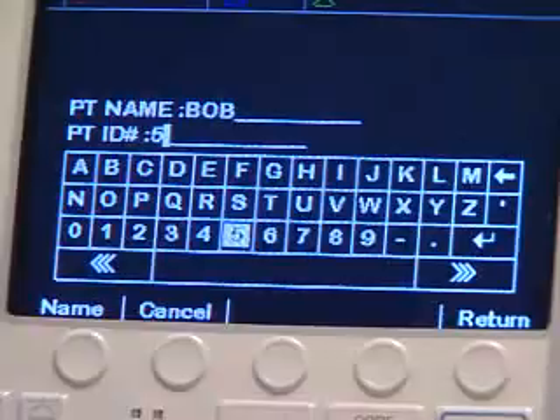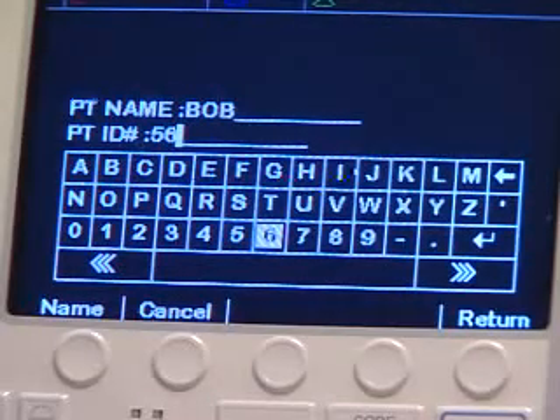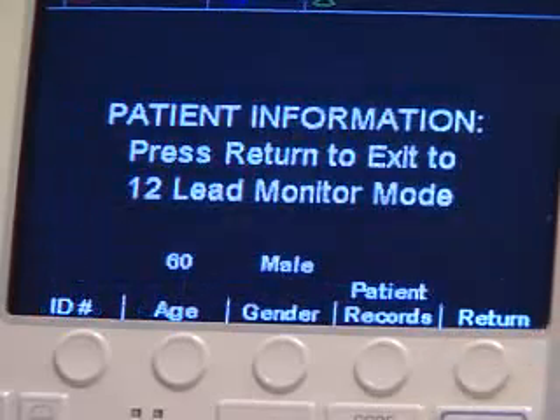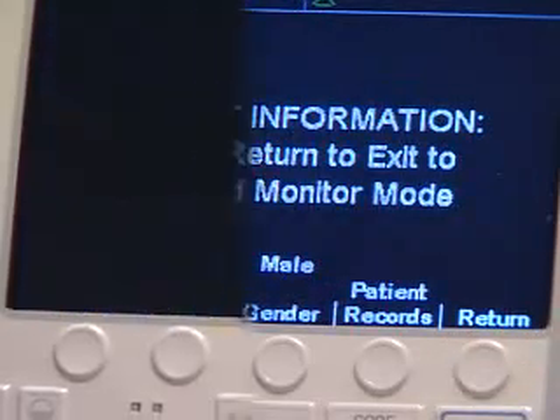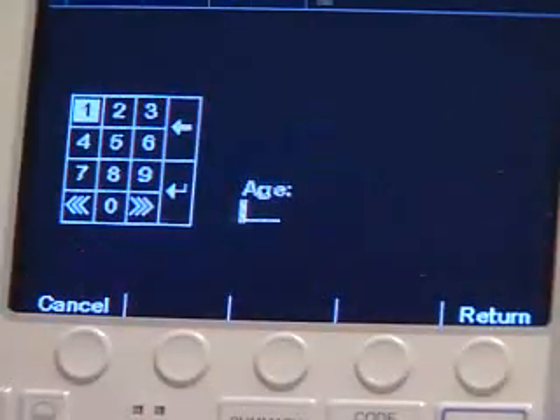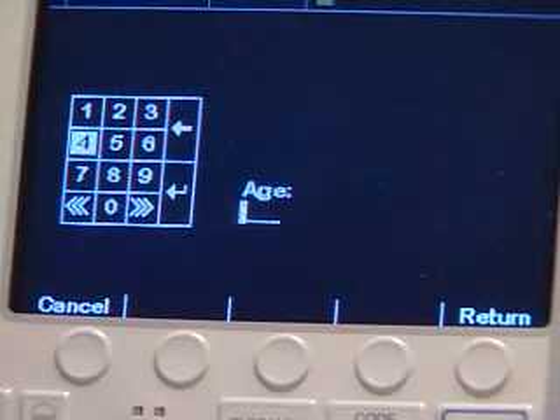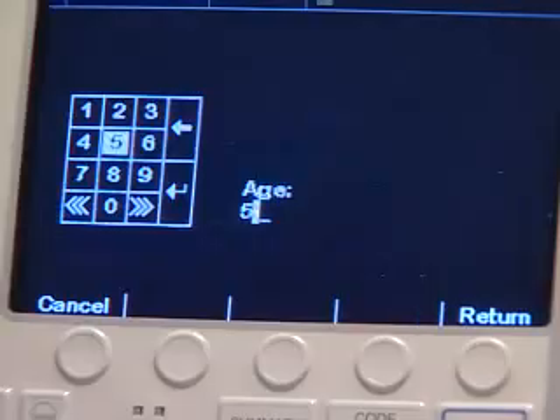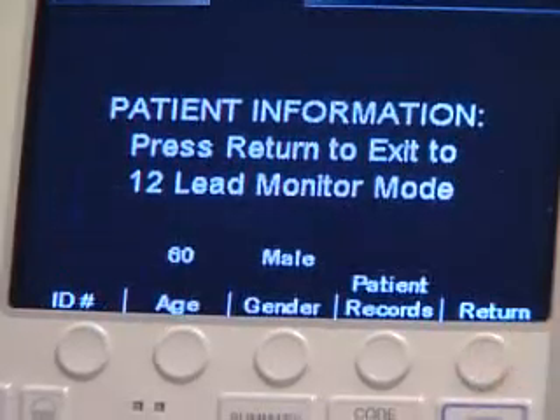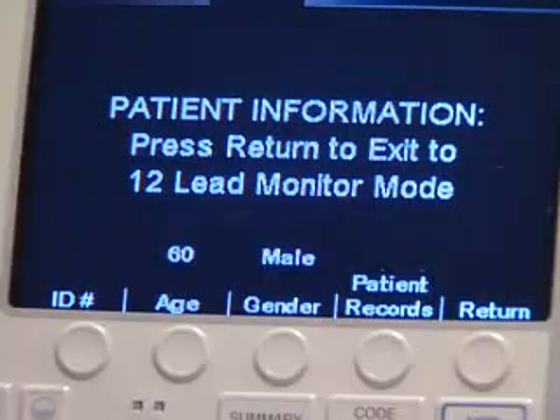The patient ID number is entered in the same manner as the patient name. Pressing the Return soft key takes you back to the patient information screen. Pressing the Age soft key allows you to enter the patient's age. Press the Return soft key to save the highlighted age and return to the patient information screen. If no patient information is entered, the default age of 60 and the default gender of male will be displayed on the 12-lead ECG report.